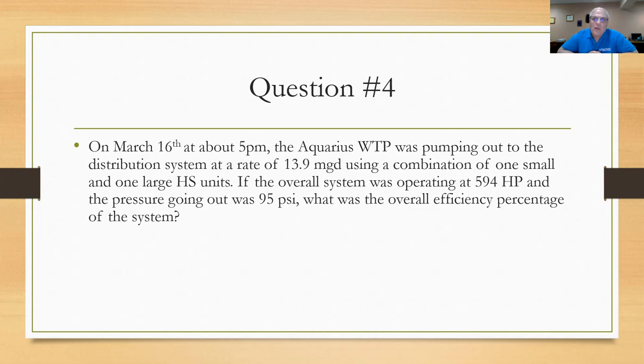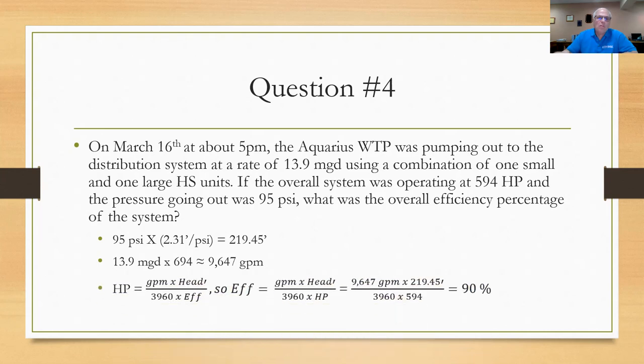If you want to try this, go ahead and stop the video now. Okay, I took the 95 psi and converted it to feet of head because remember, the horsepower formula requires feet of head, not psi. So I take the 95, multiply by 2.31, and I come up with a system head of 219.45 feet. The 13.9 mgd multiplied by 694 will give me approximately a flow rate of 9,647 gallon per minute. So I'm moving 9,647 gallon per minute out the door at a head of 219.45 feet. The horsepower we know is the gallons per minute times the head divided by 3960 times the efficiency. So if I want to solve for efficiency, I take the efficiency, move it up to the left, take the horsepower and bring it down. Now my formula becomes gallon per minute times the head over 3960 times the horsepower. When I plug those numbers in, I get roughly a 90% efficiency. Not bad.